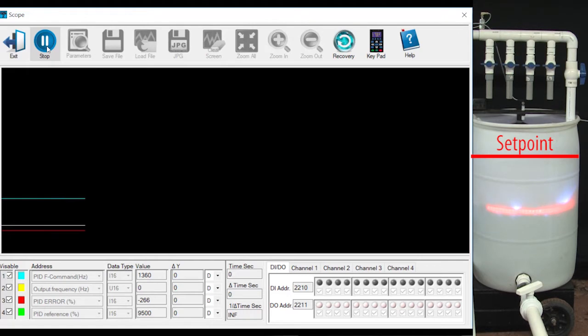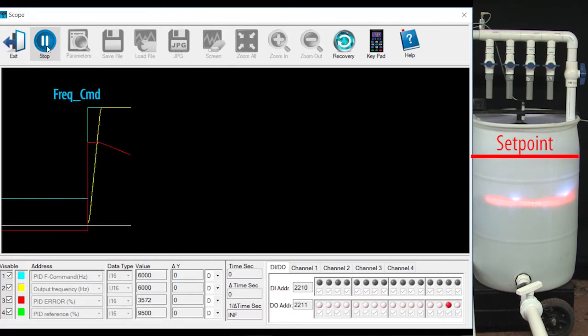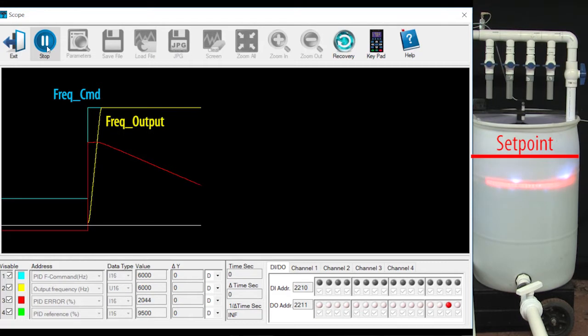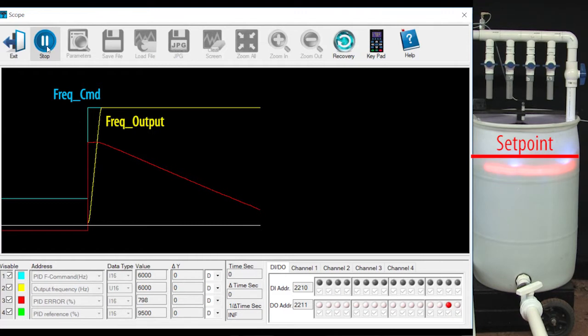When I hit run, PID sees the water level's down so it cranks up the blue frequency command and that exits the drive as the yellow frequency output, which has the acceleration ramp added in. The red line is the error – the difference between where the water level is and the set point where we want it to be.